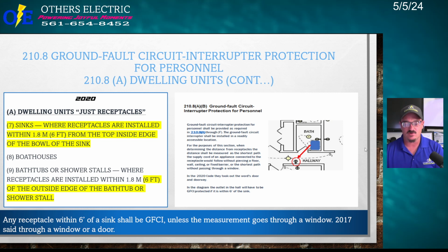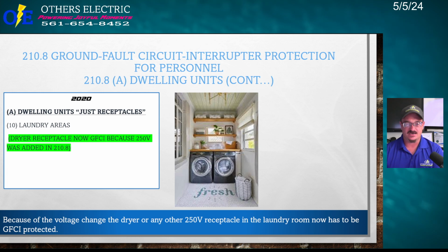So if you have a range receptacle within 6 foot of the sink, measured by a cord, it needs to be GFI protected. If it's hardwired and not a plug, like an oven, that's not what we're talking about here. We're only talking about receptacles. Things that are hardwired are not included in 210.8A because it's just receptacles. And then they added the same verbiage under 9, bathtub shower stalls: 6 foot of the outside edge of the bathtub. The only change here is how they make that measurement. There was a little confusion, and they cleared it up.